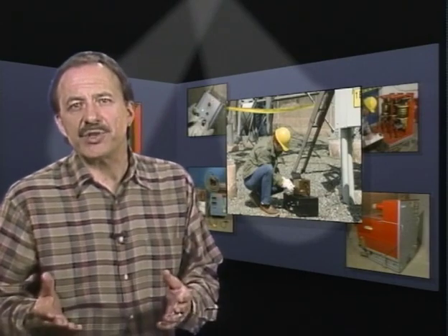Once a circuit breaker and its operating mechanism have been thoroughly inspected, and it appears that the breaker is ready to be put in service, a few tests are recommended to ensure that the breaker will function as it's designed to function. These tests, which are generally referred to as acceptance or proof tests, are what we'll look at in this last part of the program.